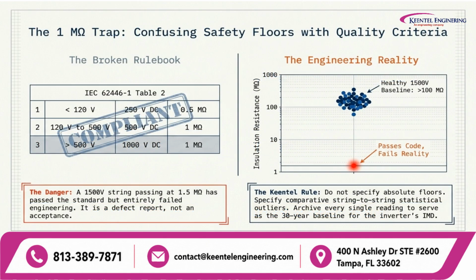One of the most widespread pitfalls in field commissioning is the 1 megohm trap. Standards like IEC 62446-1 specify 1 megohm as a minimum safety threshold. However, a healthy 1500-volt string typically demonstrates an insulation resistance well above 100 megohms. If a string measures 1.5 megohms, it technically passes the minimum code, but in engineering reality, it represents a severe latent defect. Passing code is not the same as passing quality engineering. We must eliminate arbitrary static floors in favor of comparative string-to-string statistical outlier analysis and establish true 30-year operational baselines.